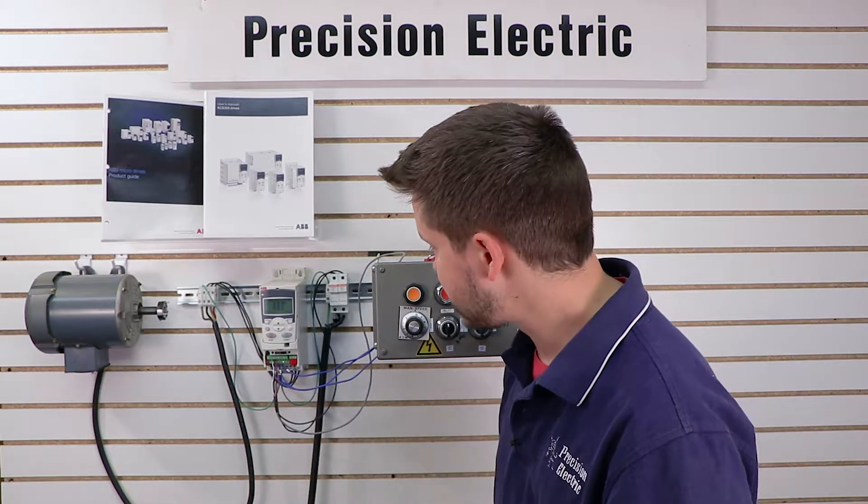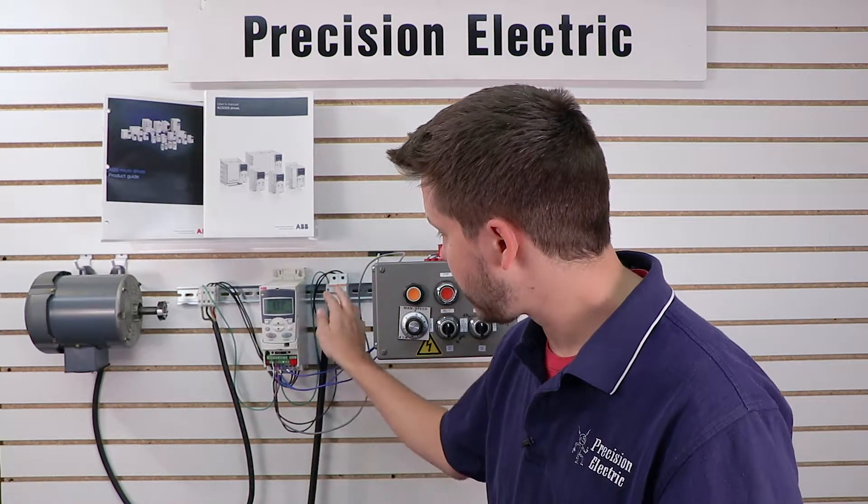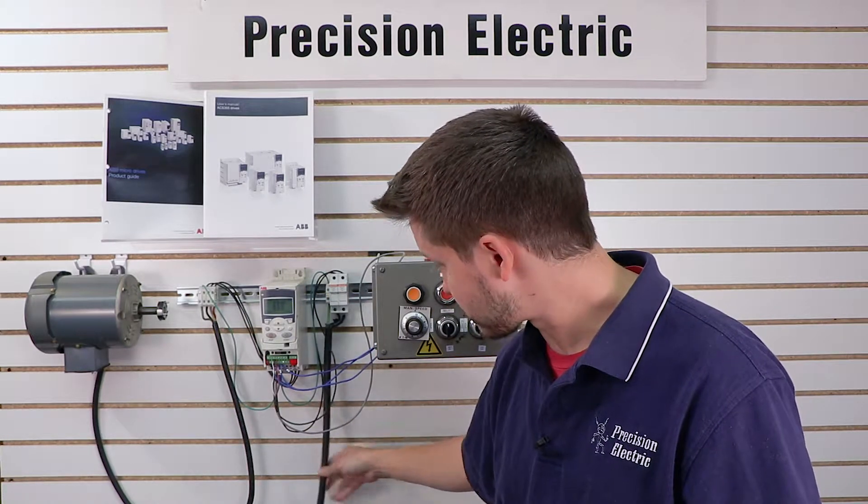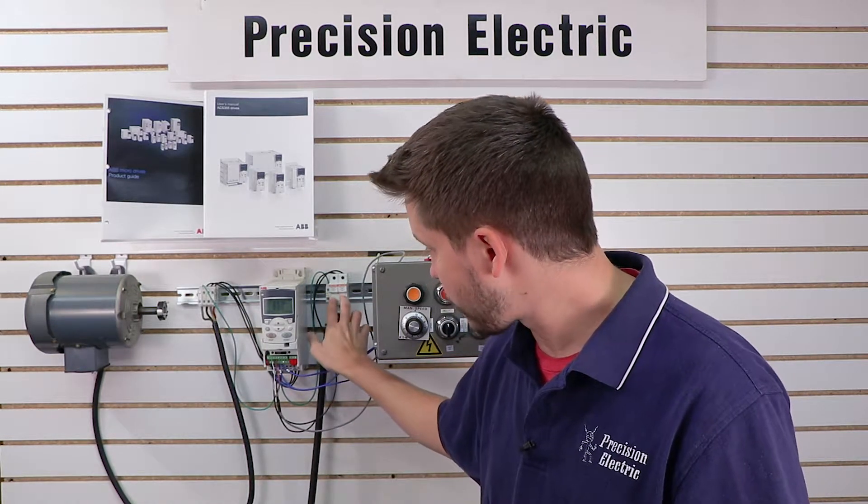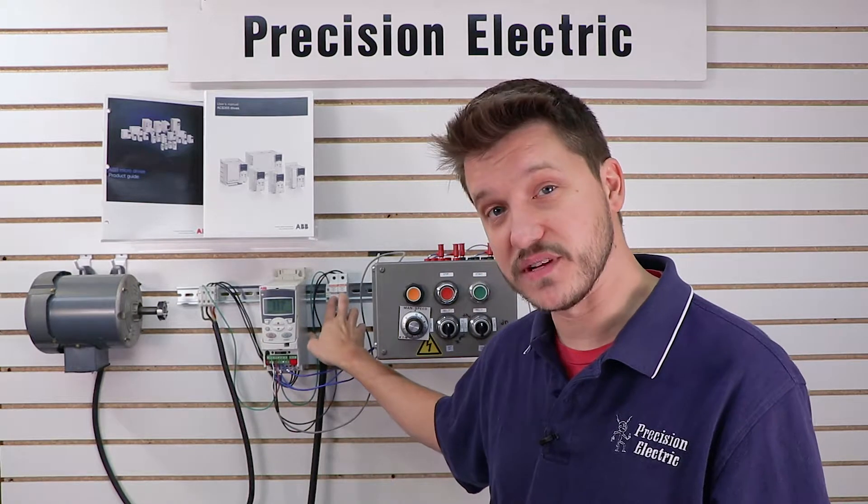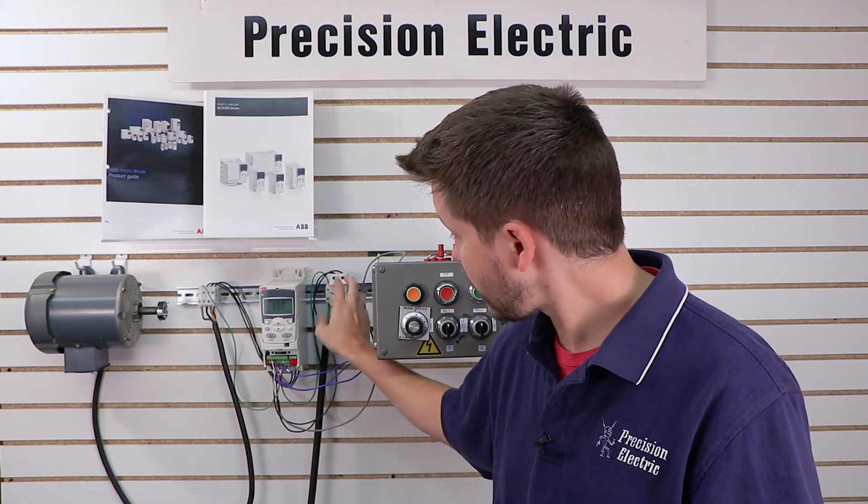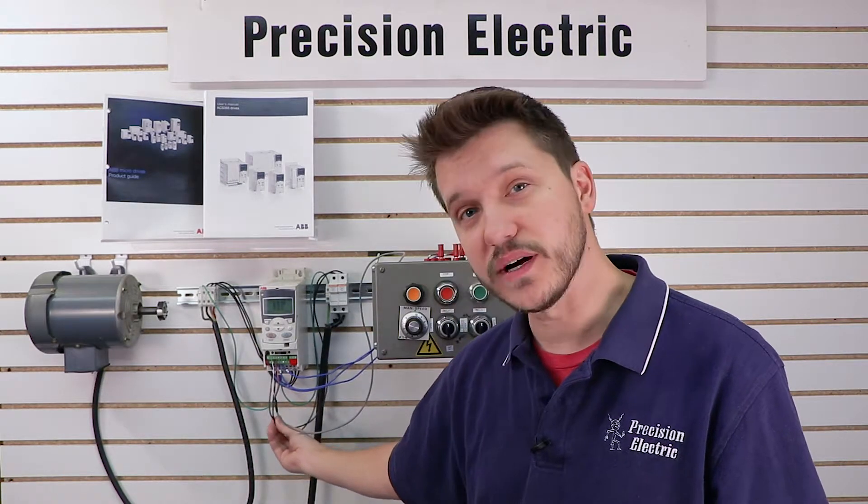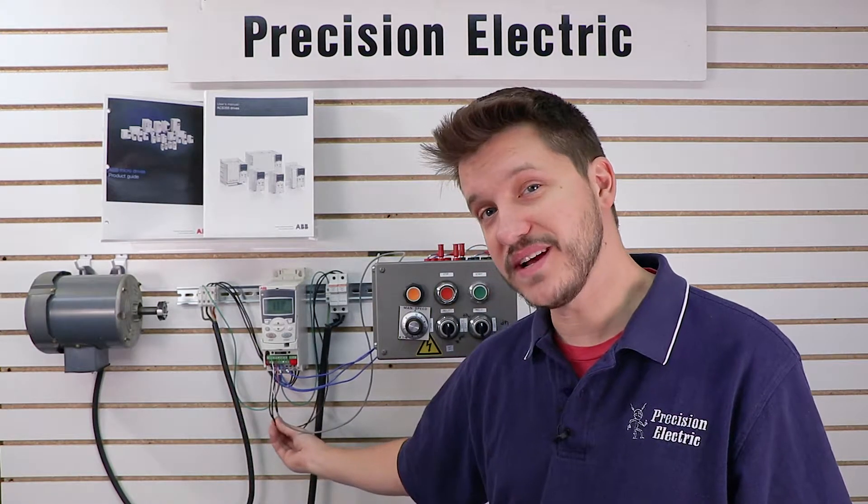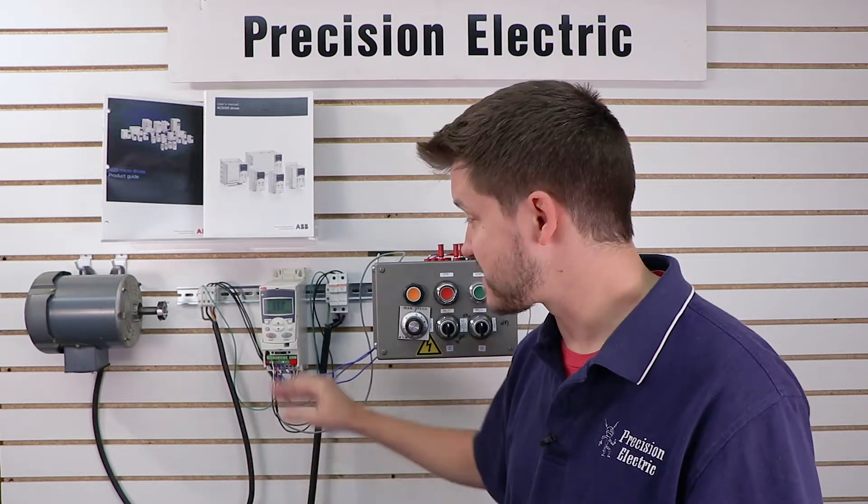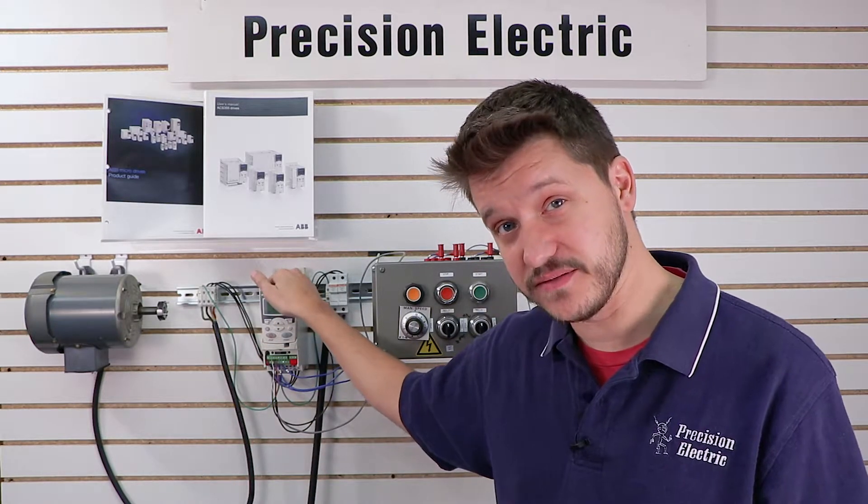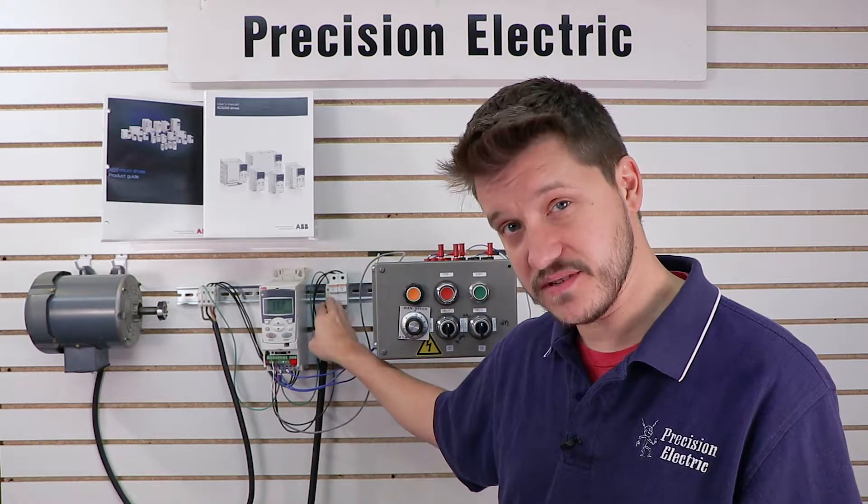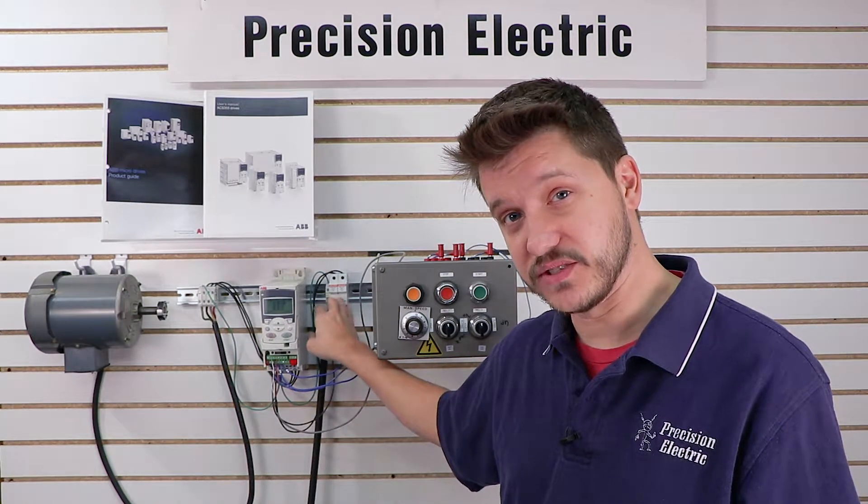In my case, I had two hot wires coming in to my drive, which is right here from my power source. And those two hot wires that are coming in, I put fuses on. I have a fuse block here. Then it comes out from the fuse block into U1 and V1. Notice I don't have anything on W1. That's because this is a single phase drive, not a three phase.